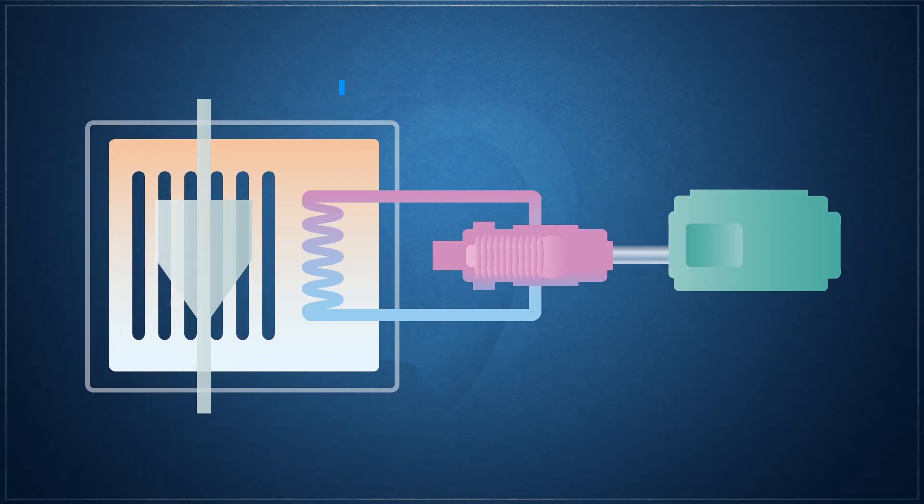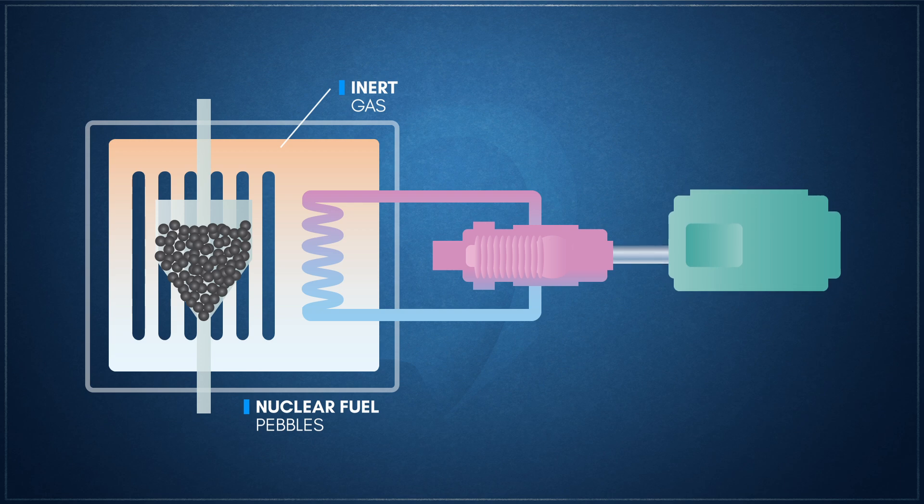Pebble bed reactors are a unique design that are powered by spherical tennis ball-sized fuel elements called pebbles. The outer shell of these pebbles are composed of pyrolytic graphite, which not only serves as a neutron moderator, but also forms a structural containment shell around the fissile material that is twice as thermally conductive as copper, immune to corrosive effects, and can withstand high stresses and temperatures exceeding 2000 Celsius.